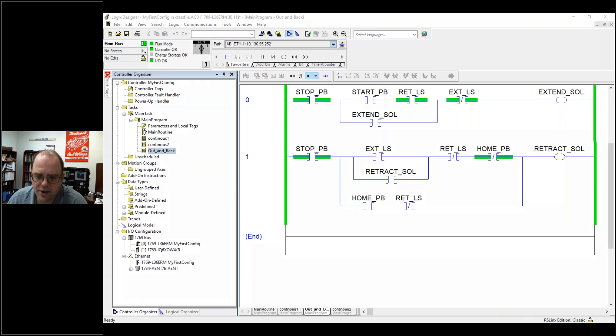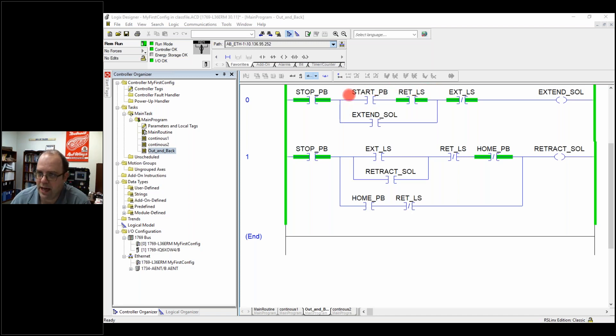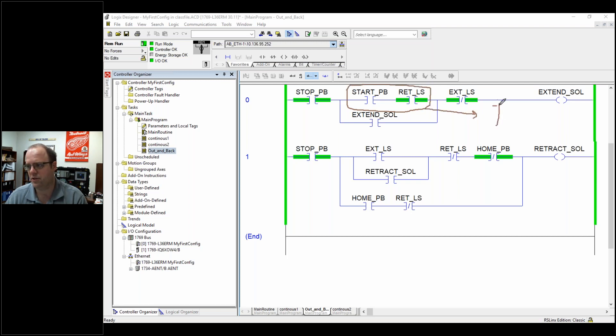If you look at what's on the screen, I have my stop button right here, and that's in line with everything else. Then I have a start push button. Here's my seal-in — we've done this before. But remember, before my cylinder retracts, it's hitting the retracted limit switch. If I want my cycle to always start in the same position every time, I need to put things inside my seal-in so that when the initial conditions are met, this happens. Think of this as: for my starting process, anything in the seal-in will be my initial conditions.